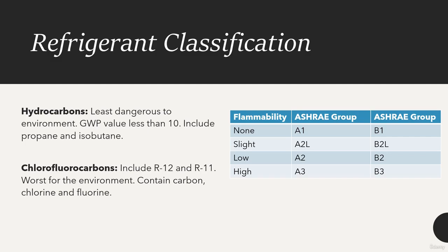As you look to the right, you can see the ASHRAE ratings on flammability and toxicity of refrigerant. And what you're seeing a lot in today's industry is the move into A2L type refrigerants, which are your more flammable refrigerants.